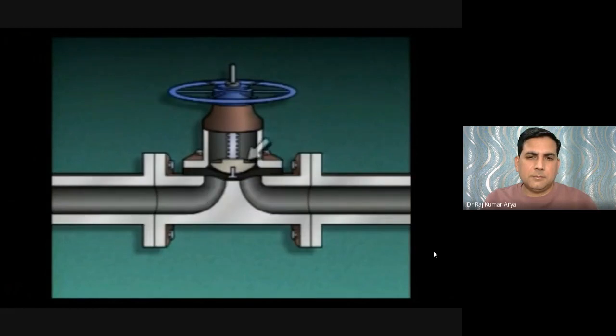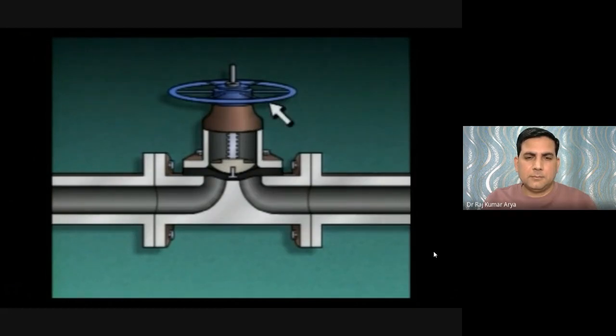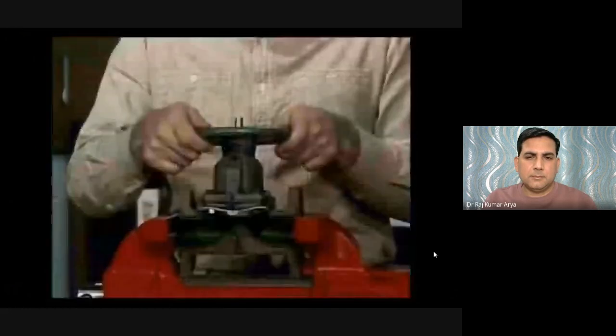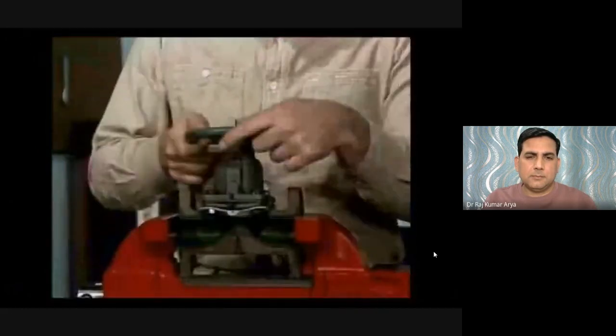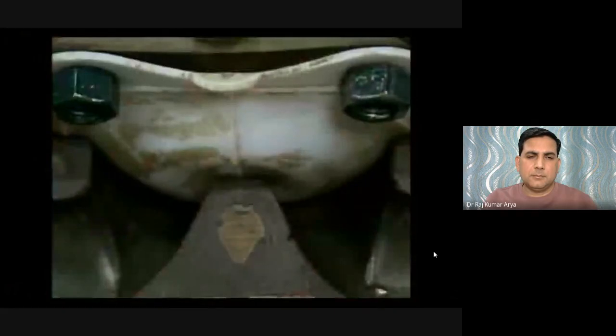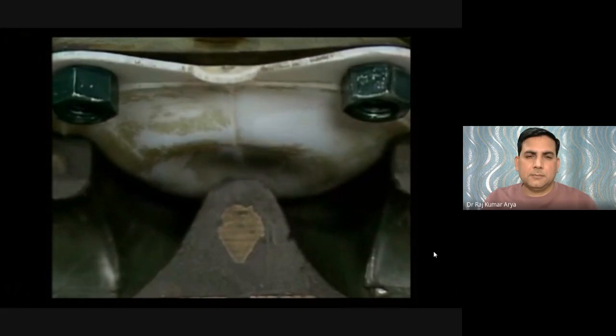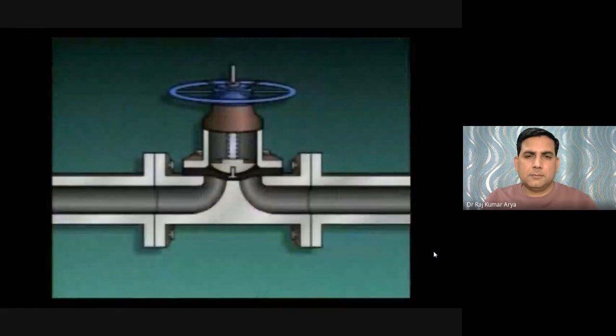The plunger is worked by the valve stem. A hand wheel is used to raise and lower the stem. When the hand wheel is turned clockwise, the stem and plunger lower the diaphragm, pressing it against the seat to stop flow. When turned counterclockwise, the diaphragm moves upward and flow through the valve can begin. A diaphragm valve can be used for both on-off and throttling purposes.